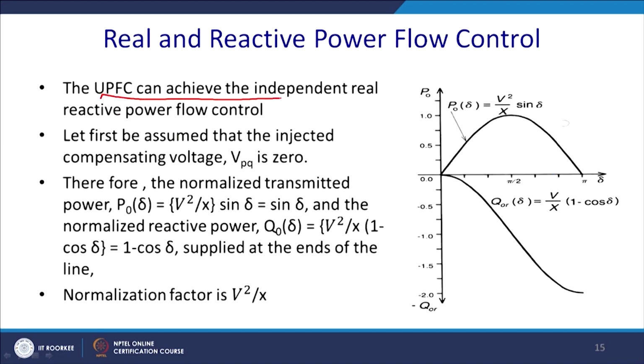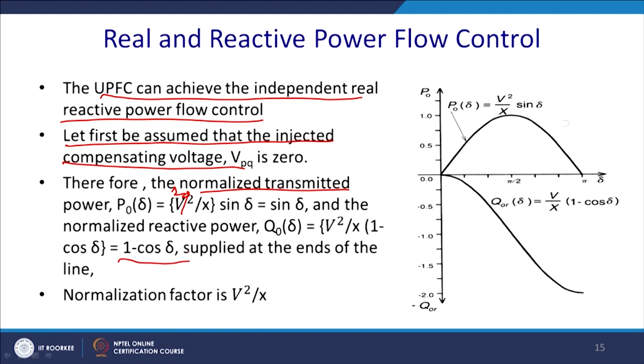The UPFC can achieve independent real and reactive flow of power through the transmission line. That is one of the basic requirements. Let us first assume that the injected compensating voltage V_pq is 0. We are not injecting any voltage. Therefore, the normalized transmitted power is V square by x sin delta. We consider this value to be 1, thus we are left with sin delta, and the normalized reactive power is V square by x (1 minus cos delta). So, we are left with 1 minus cos delta, supplied by the end of the line, and we normalized this value to be 1. So, we have these two curves which we have been discussing from the beginning of the classes. So, what happened here?